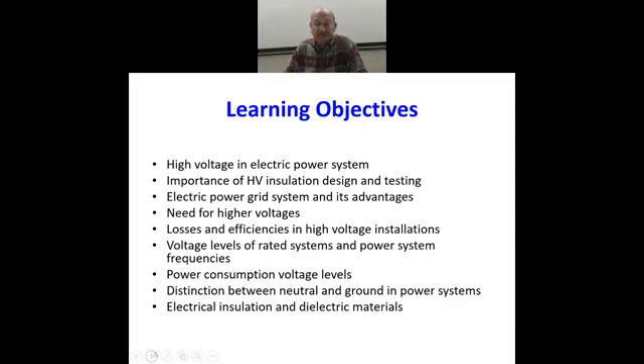More than 100 years back, it was thought 110 kV would be the highest transmission voltage. But we do have today in the world 1150 kV transmission voltage. In the past 50 years, the leap in power systems has taken place. It is nothing but because of the high voltage availability and application, and that is how we are able to handle very large demand of power. We are able to generate the power, transmit the power, and bring it to the consumer by what we call distribution.